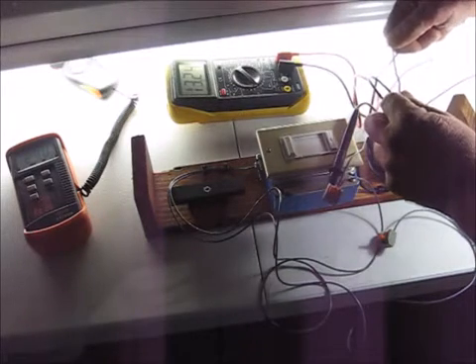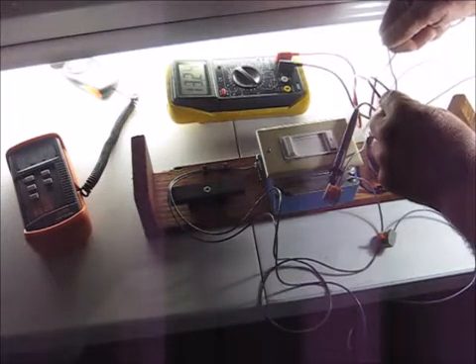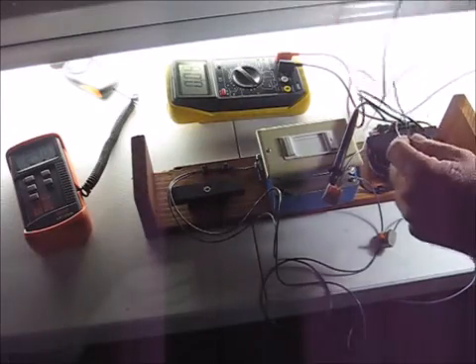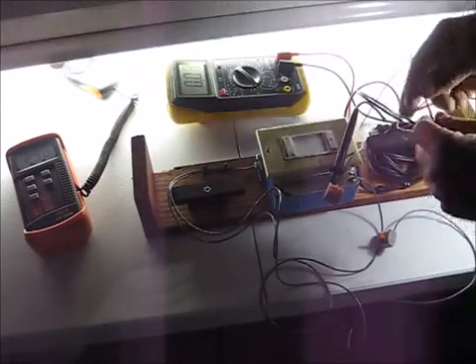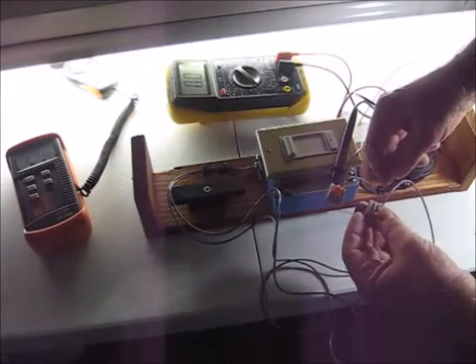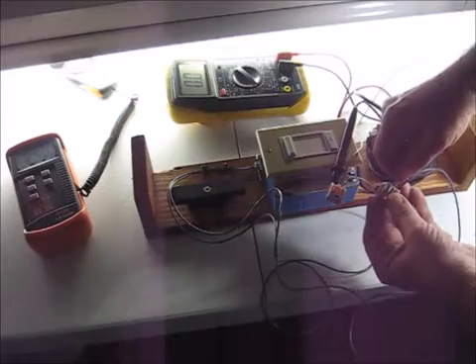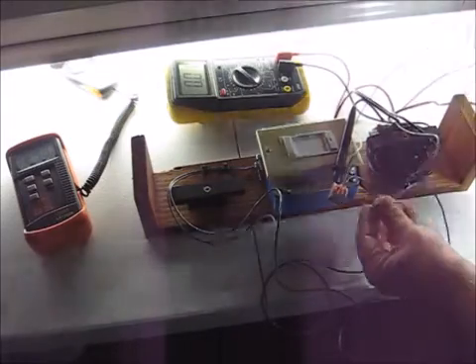I've got a 13 and a quarter volt open wire voltage. Now this is different than the last one of these I checked. So this is probably a newer ballast. They probably made some changes. But this one should be fairly fresh.